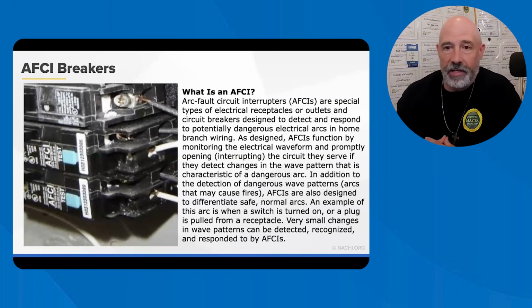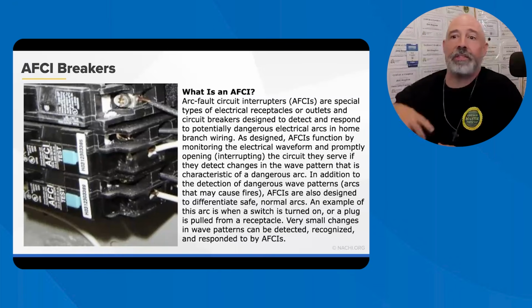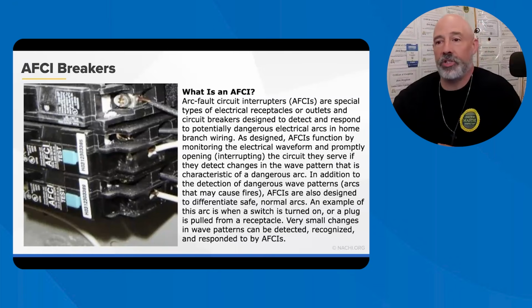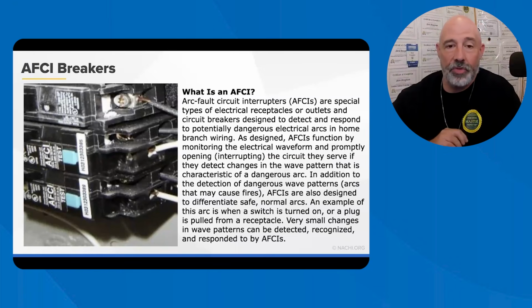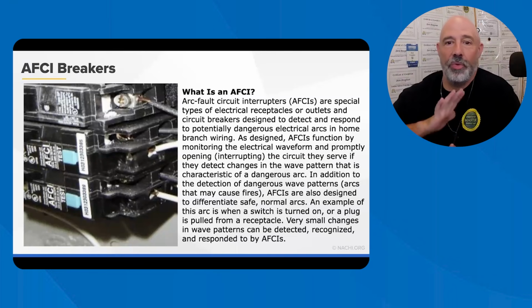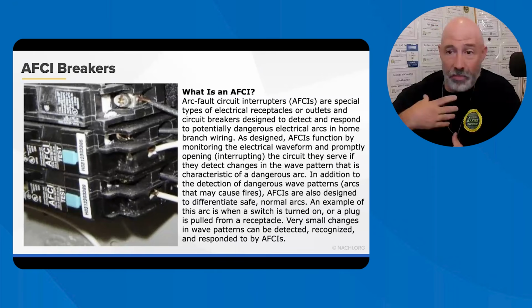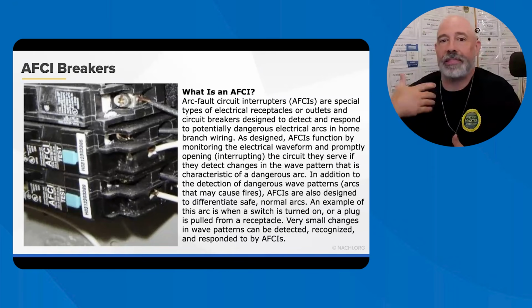AFCI breakers, kind of the same thing. I want them to trip them at least twice a year. These were in new construction since 1999. In addition to the NEC, many jurisdictions are now observing this as a required code addition, which have expanded use of AFCI devices to almost everywhere in the dwelling. So these breakers are designed to trip if they sense a fault.